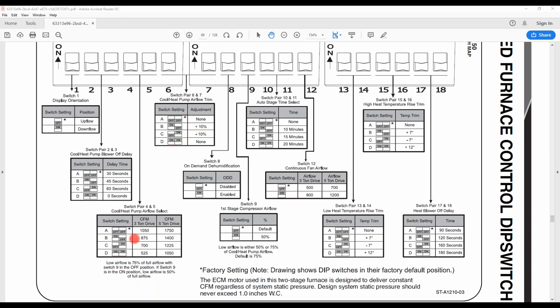Should you want a full 1,200 CFM on a 3-ton drive, you will want to take switch 6 and 7, take 6 to the on position, 7 leave it in the off position. You will now increase your cooling airflow by 10%. At that point, you will be fully moving approximately 400 CFM per ton. If you want to decrease it even more for more dehumidification or for additional airflows, you can decrease it by 10%. Switch 6 is in the off position. Switch number 7 is going to be in the on position.